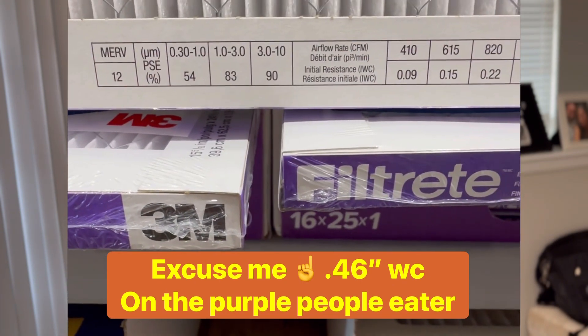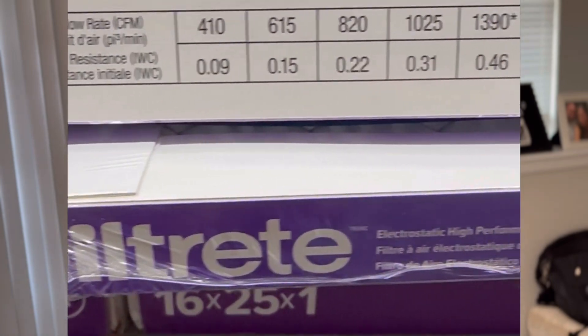I was amazed — and I think this might be something new that Filtrete started doing — they actually publish the initial pressure drop across the filter on the side of the box. Something I haven't seen in years past. The 3M Filtrete, the purple or blue one, has a 0.46 inch of water column drop across the filter when clean. Let me explain what that means.